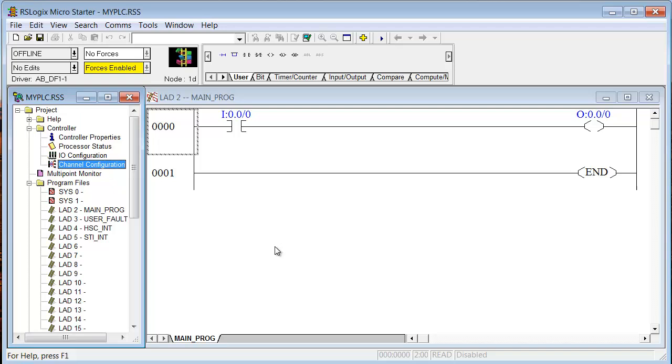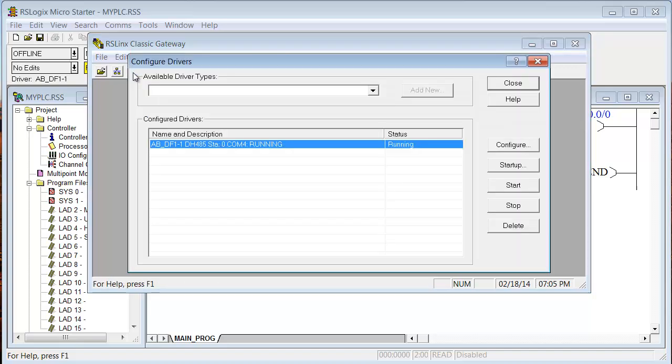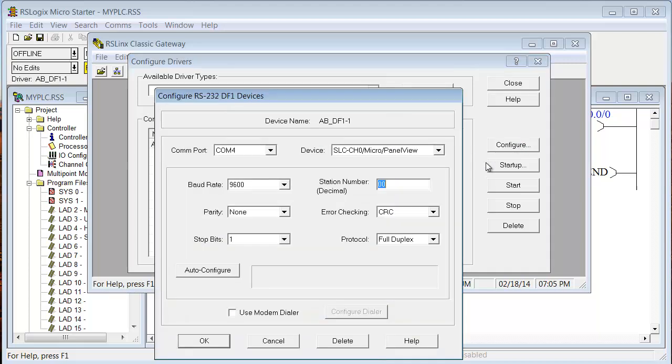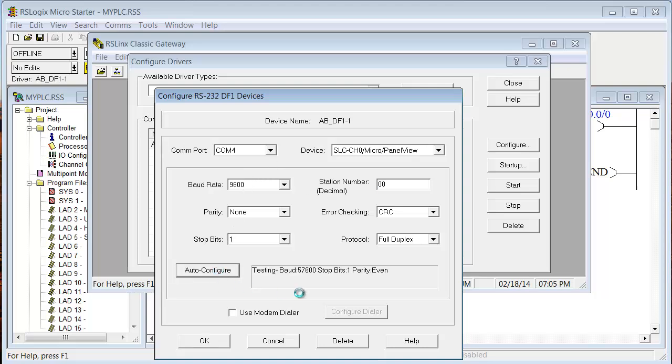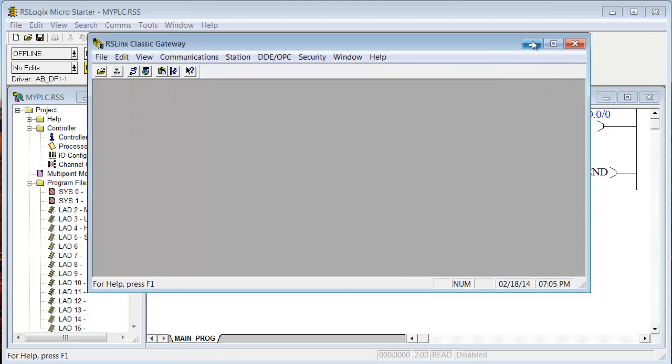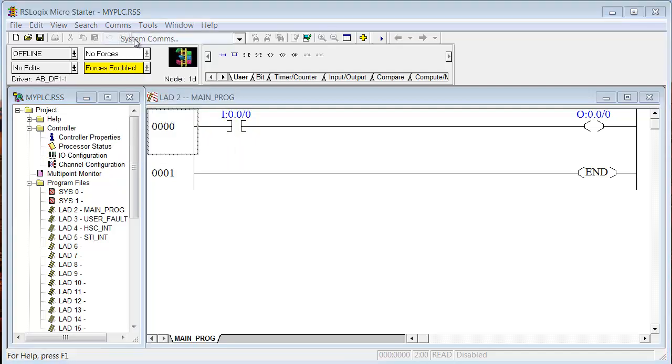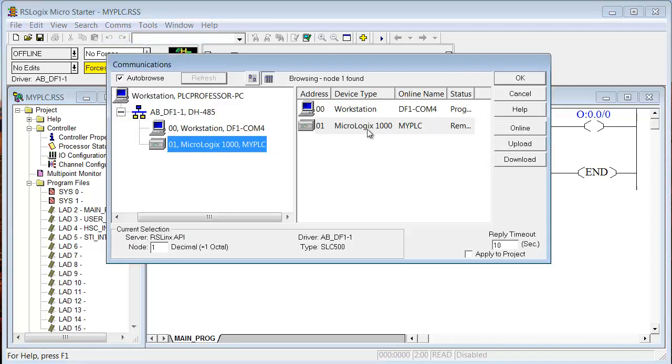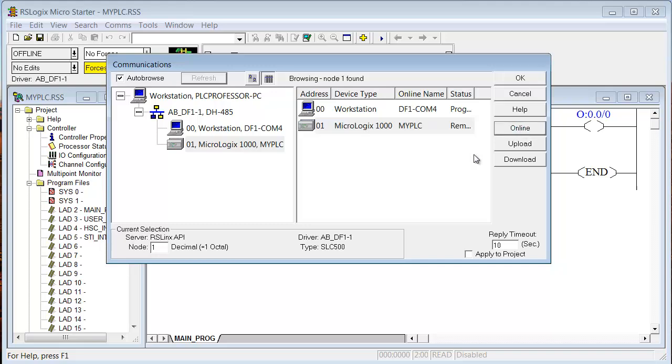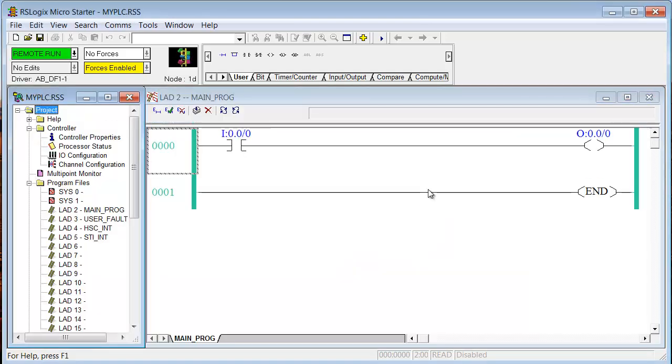with the RSLinx driver the way it's set. So let's open up the RSLinx driver again. Now that we have the RSLinx open again, let's go to this driver. Go to Configure. See, it's still set at 9600. So when we do Auto Configure, this time it should find 19.2. See, Auto Configuration Successful, 19.2. Now we click OK. We can close down RSLinx, and now we can go back online. System comms, online. Save changes, yes. After all, we did change the baud rate, and that is part of the configuration. So see, now we're back online. We're back online with RSLogix, MicroStarter, and MyPLC.